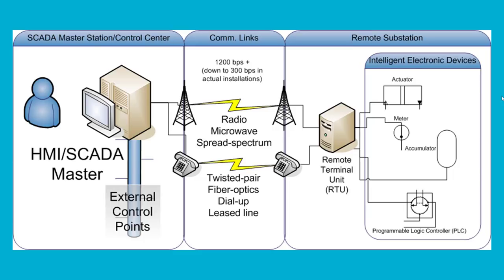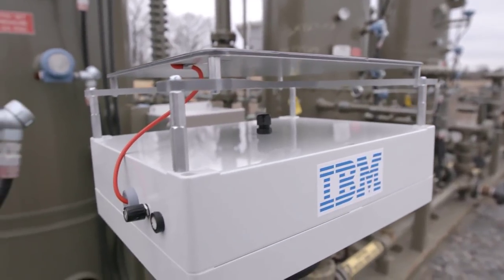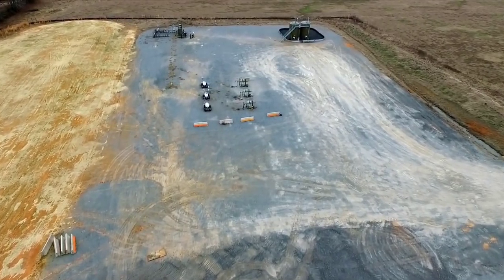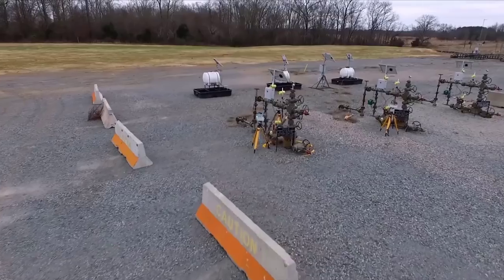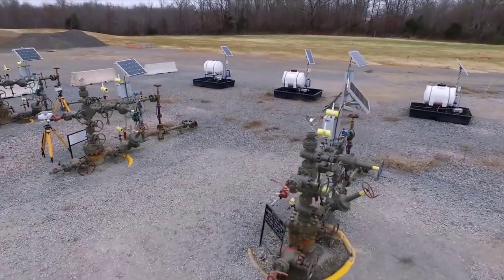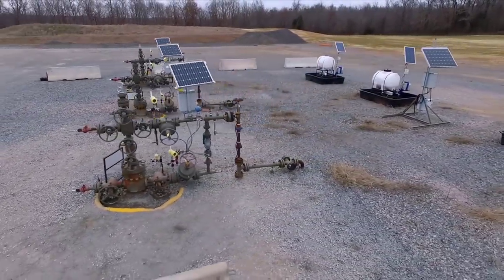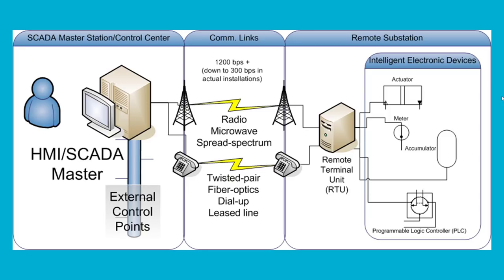Now you might be thinking if we have a PLC — PLC is doing the same job — why are we looking for RTU? RTU is made for harsh environments where PLC cannot actually bear that kind of environment. Like maybe you have a wellhead site, or an oil well that's very far away, maybe in a desert. If you are trying to get the data from that point, you cannot rely on the PLC in that particular harsh environment. So in that case, we need to have an RTU. The whole purpose of RTU is that it is built for harsh environments.